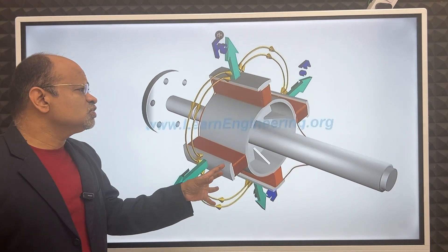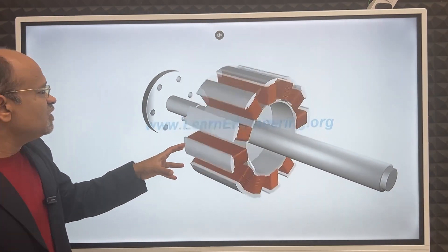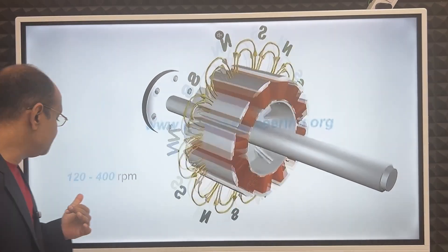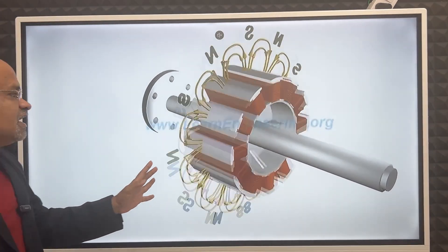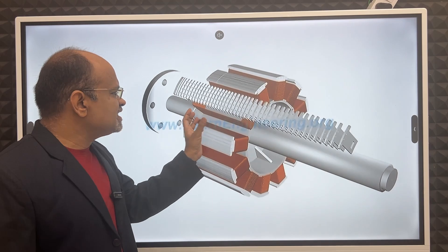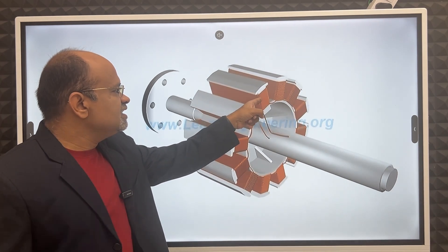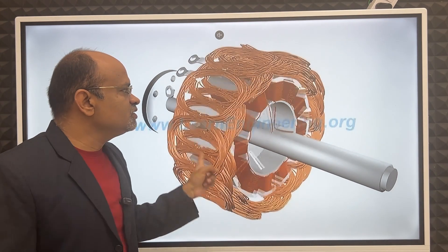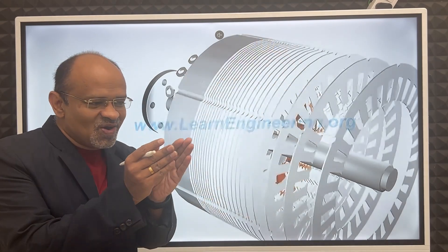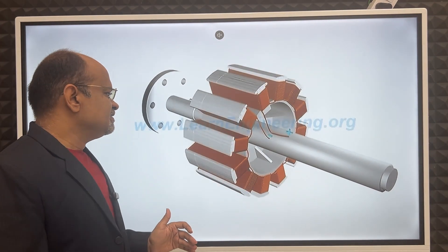If we use fewer poles, the rotor can split apart due to centrifugal force, so we use more poles to reduce speed — for example, 400 RPM with more poles. The laminations or stampings in the stator are used because eddy currents form in metal just as they do in coils. By using thin stampings, the eddy current is reduced to a negligible level.